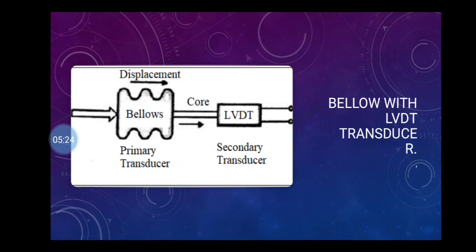Due to the displacement, the bellow does elongation and contraction. Now this is the input of the LVDT, and the LVDT gives the output, and this output is measured by the pressure gauge. Thus the input pressure which is to be measured is conveyed through the primary and secondary transducer, is calibrated at the output end, which is read by the pressure gauge.